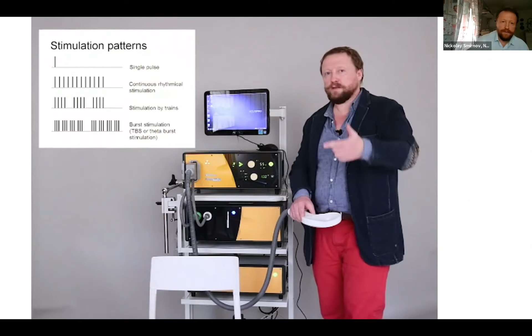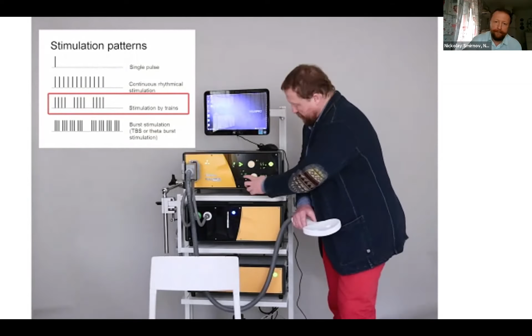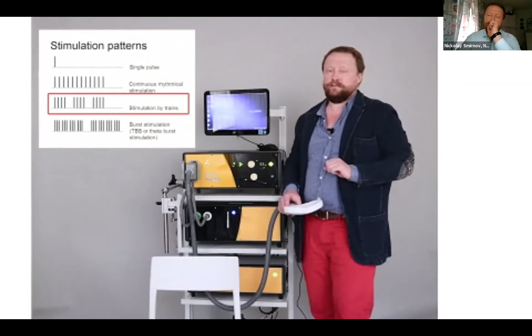The next mode is stimulation by trains. Here I set the frequency, which is 10. I can change it; for example, now I will do 9. Then I can set the train time, for example, 3 seconds. Then I can set the pause time, and then I can start stimulation. Now it will stimulate 9 pulses per second. It will make a 3 second train, and then a 2 second pause, and so on and so forth.